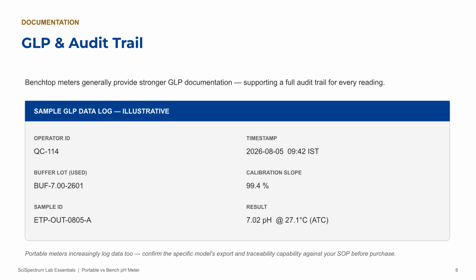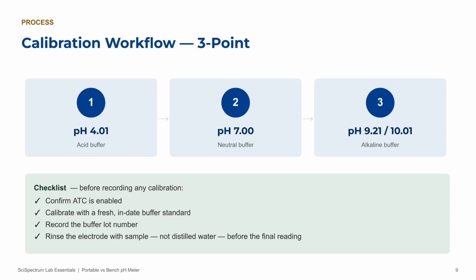Portable meters are catching up and increasingly log data too. But if your SOP requires printed GLP records or NABL traceable calibration tied to every single reading, double-check that specific model's capability before you buy. Calibration itself is pretty similar across both instrument types. You're doing a 2 or 3 point calibration against standard buffers, typically pH 4.01, 7.00, and then either 9.21 or 10.01. What differs is the context it happens in.